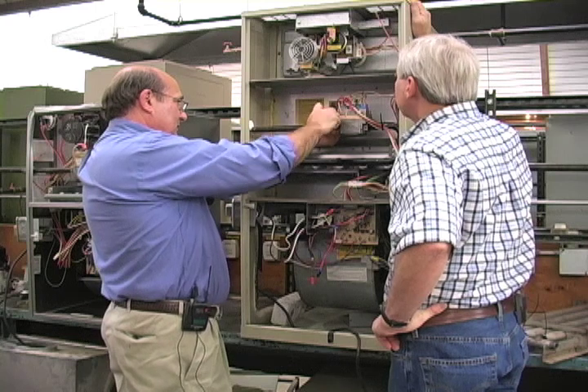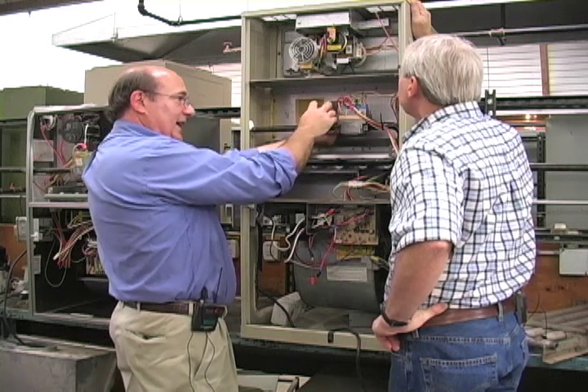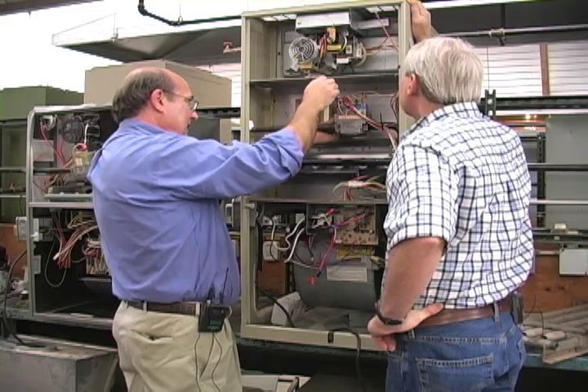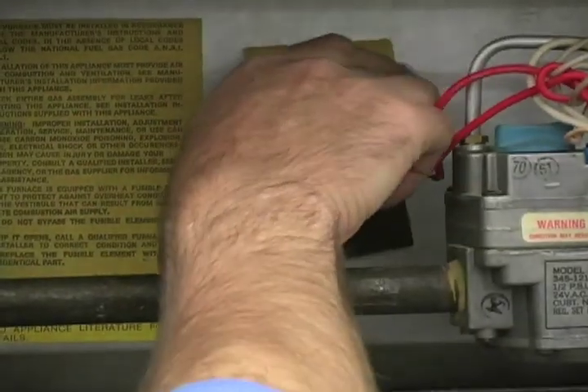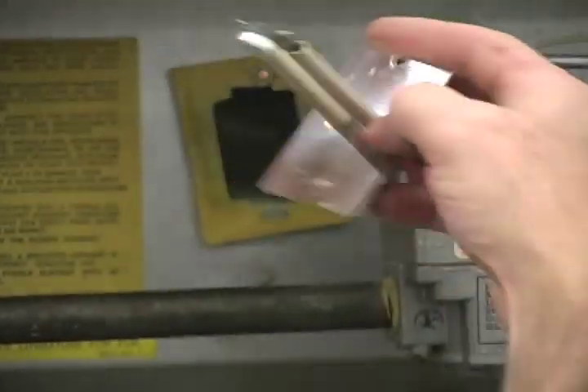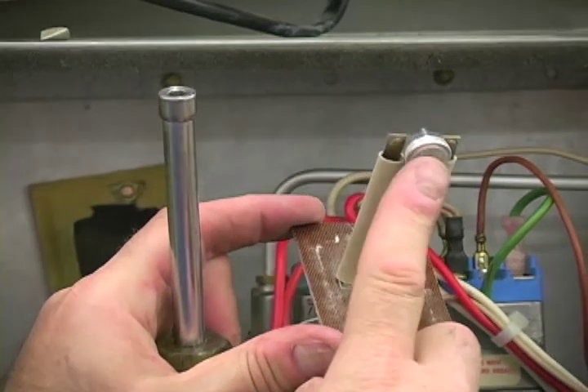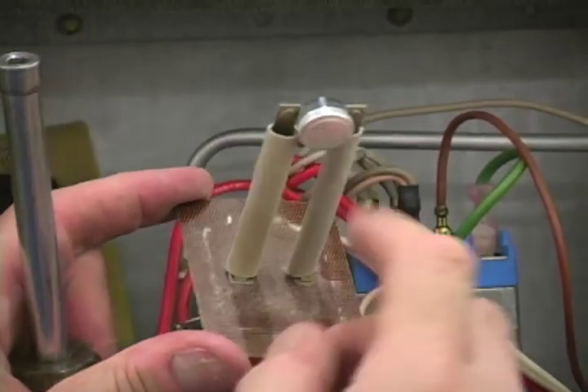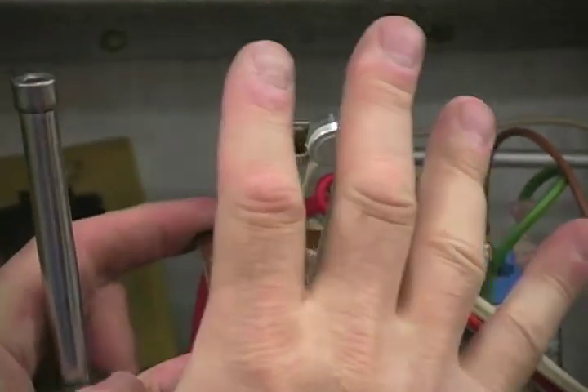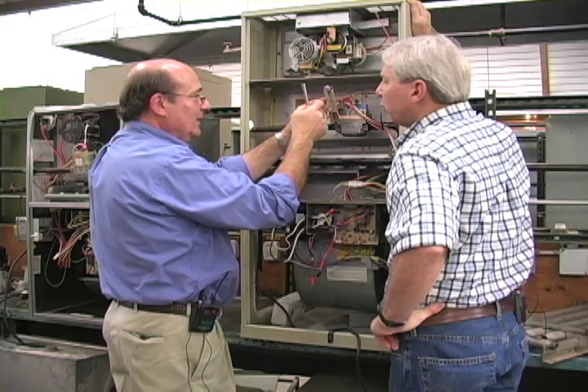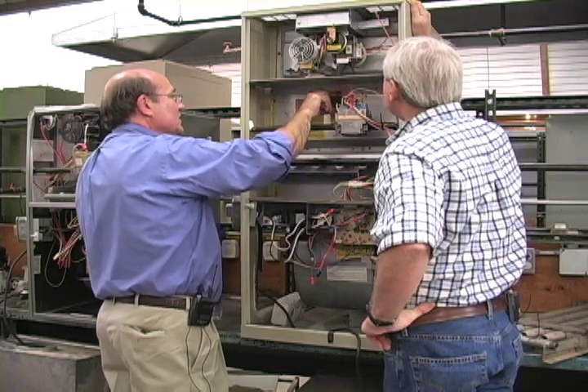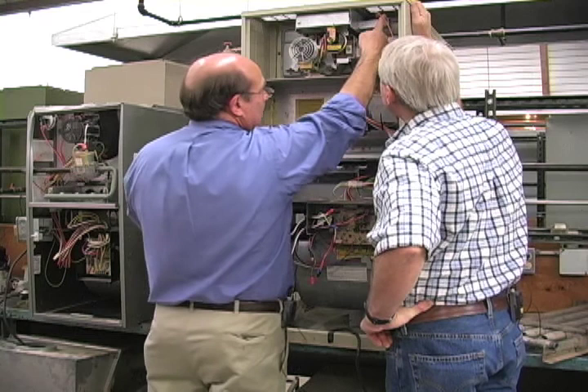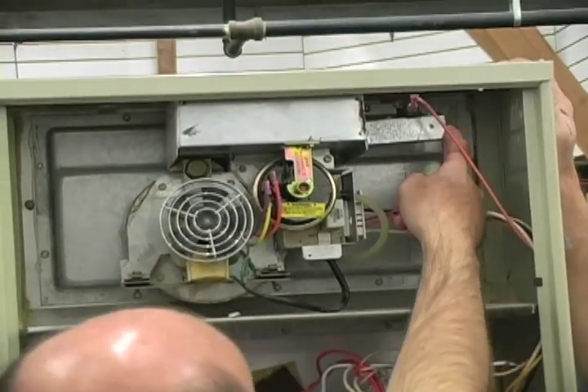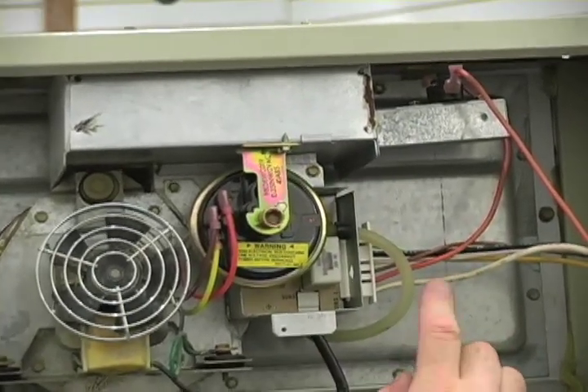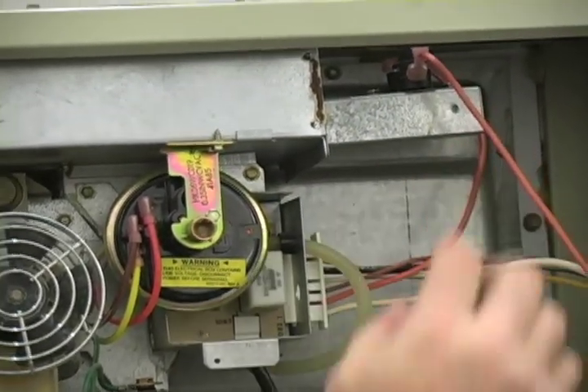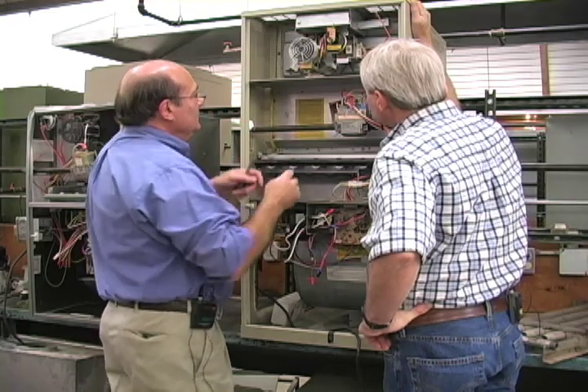And that is, we looked at that limit switch on that other furnace. That turned on the fan, and it maintained the gas pressure on this. I'm sorry, safety, yeah. Right. This one has a different style. It's called a snap disc. This is a little element over here that if it gets overheated, it will cause this little disc inside to snap open. It's like an old-fashioned clicker type thing. Breaks the circuit, shuts down that gas valve as a safety. We have the same type of switch right up in here. This is on the exhaust side of the combustion blower motor. If for some reason the exhaust gas temperature got way too high, that would shut down the gas valve as well. So those are the two safeties.